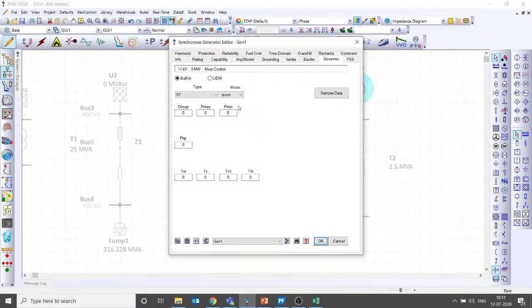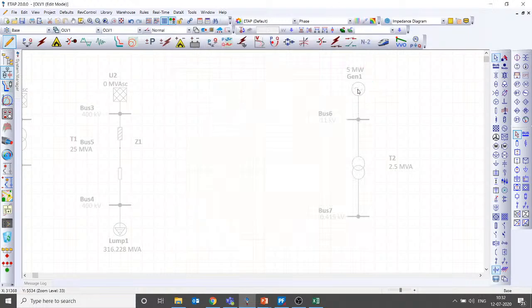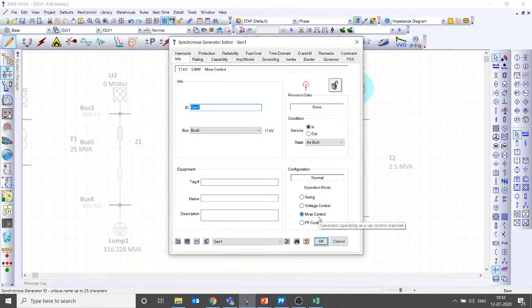Yeah, what is the difference between MVR control and power factor control? That's a good question. MVR control and power factor control seem almost the same in ETAP, right? But there is a difference. If you put it in MVR control, irrespective of change in the real power, the reactive power Q is maintained constant. For example, take a 500 megawatt generator. If you put the generator in MVR control mode and fix this Q value at 200, then because of grid frequency changes, or governor operations, droop, or whatever the reasons, if the real power changes, this reactive power remains 200. There is no change in it.